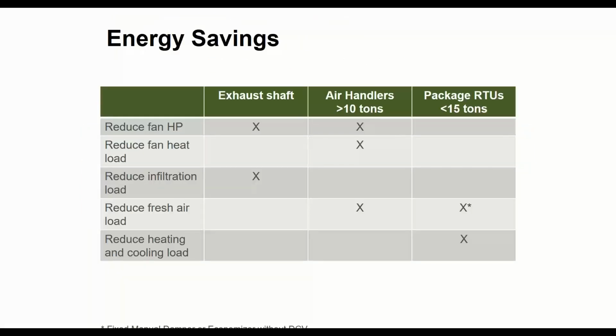So typical applications for duct sealing needs on exhaust systems. If we have duct sealing completed on those type of systems, whether it's Aeroseal or whether it's done by hand, you can reduce the fan horsepower of that fan, basically put a smaller fan in or slow your existing fan down, and you can reduce your infiltration load on the building.